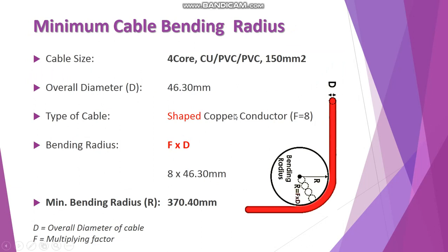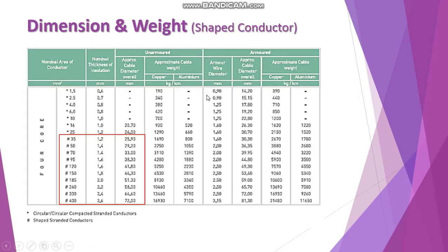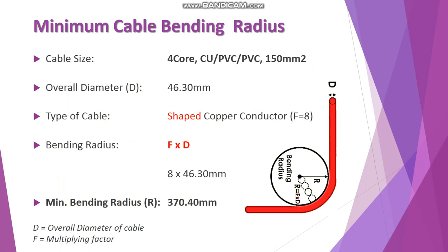Now let's take an example of a shaped conductor. Here we take the example of a four-core copper PVC/SWA/PVC 150 mm² cable. The overall diameter of this cable is 46.30 mm, as taken from the dimensions and weight table for shaped conductor cables ranging from 35 to 400 mm². Since we are using a shaped conductor, the multiplying factor is 8. So: R = 8 × 46.30 = 370.40 mm. We cannot bend this cable less than 370 mm, otherwise it may get damaged.